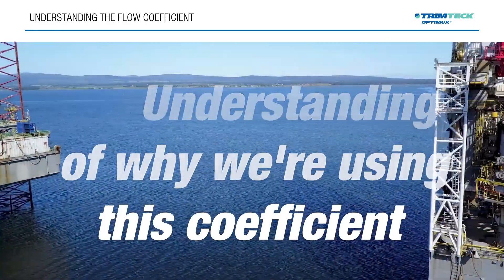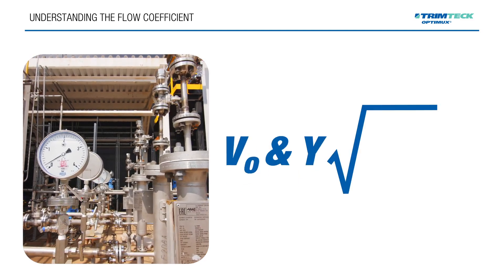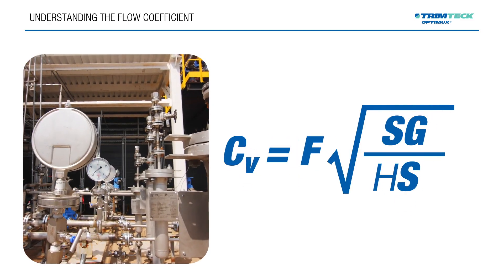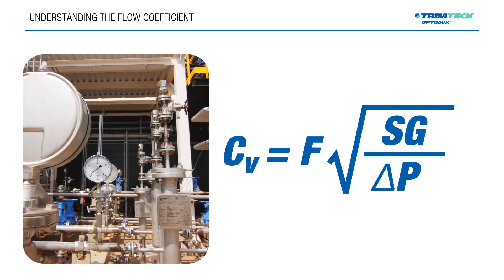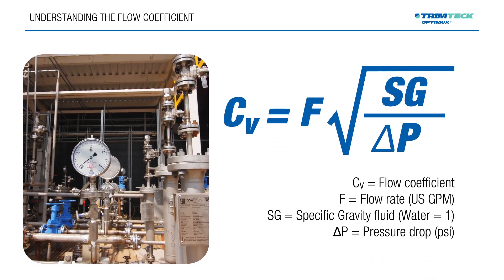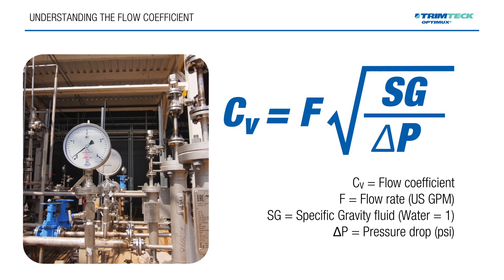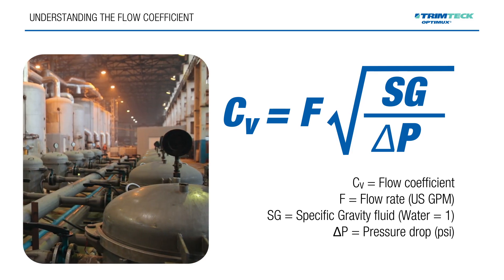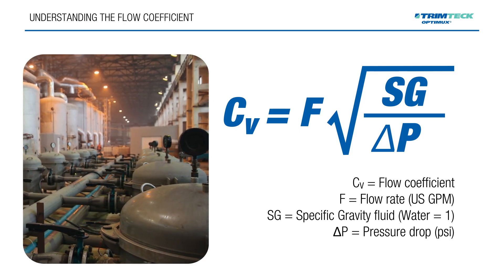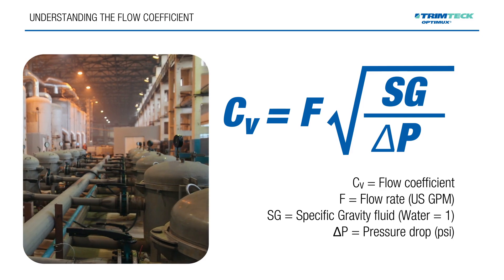The formula is often seen but not always understood. CV is equal to the flow rate times the square root of the specific gravity of the fluid over the pressure drop. Let's dive into the formula so as to better understand the coefficient.